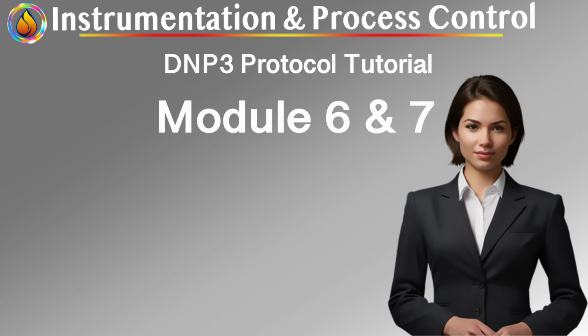7.6 Application Layer Confirmation. Purpose: application layer confirmations validate successful semantic processing, not just frame delivery. They confirm that a request was correctly interpreted, the requested function was executed or queued, the response is authoritative. Use cases. Application confirmations are especially critical for control operations, unsolicited responses, time synchronization, configuration commands. Failure to receive confirmation triggers controlled retry behavior.